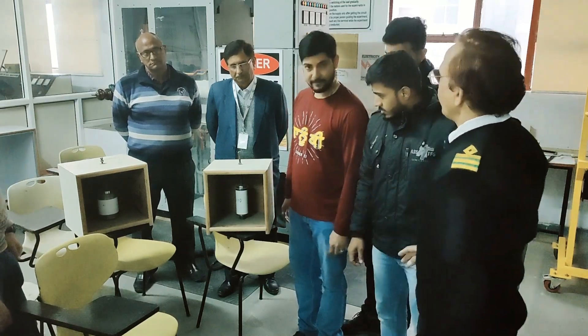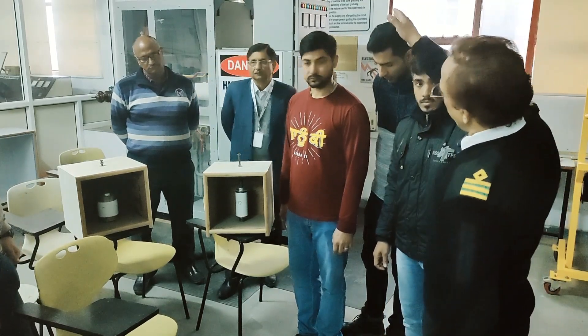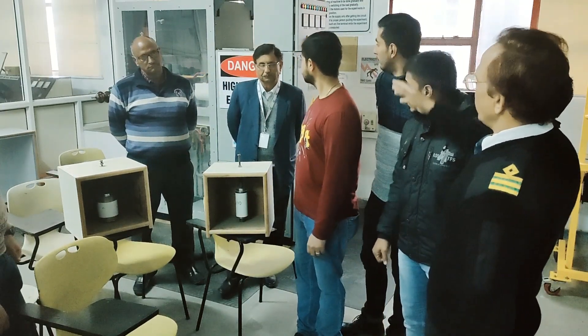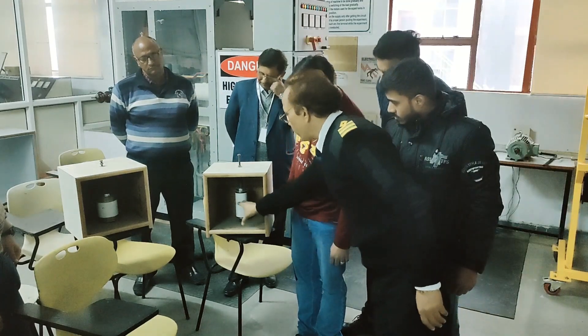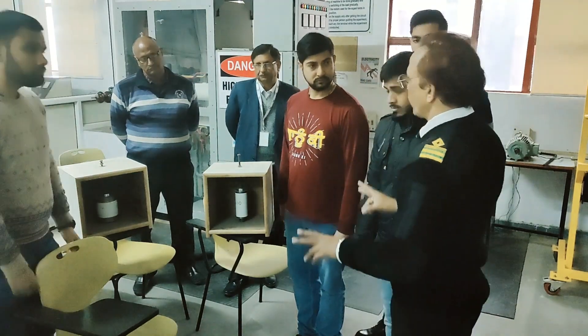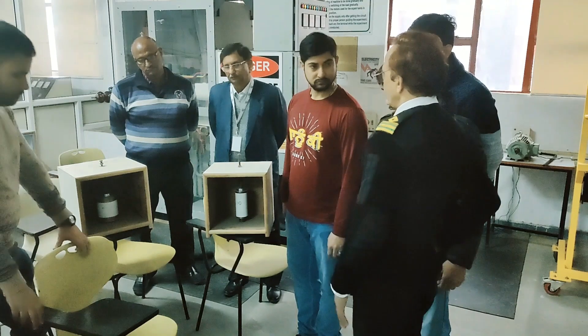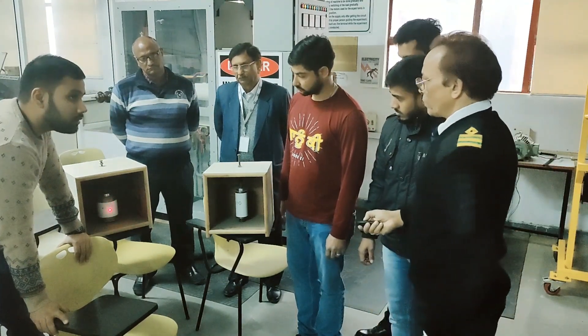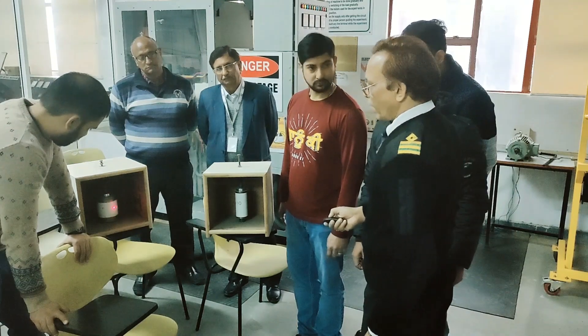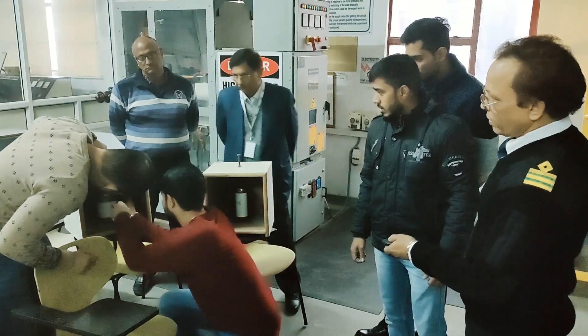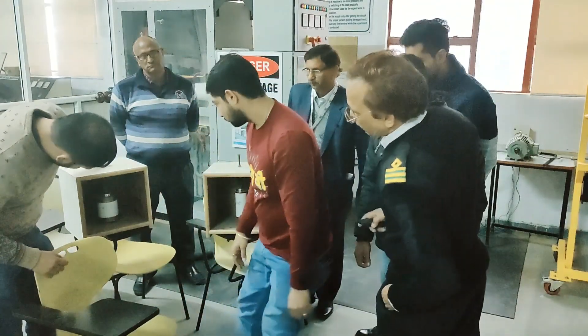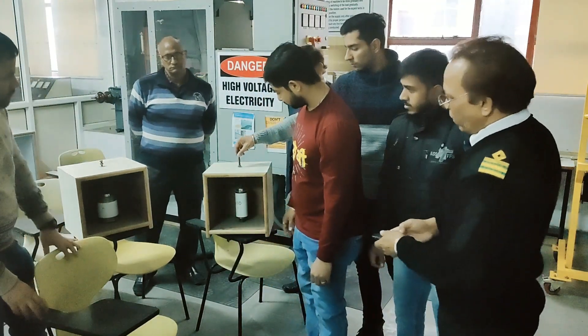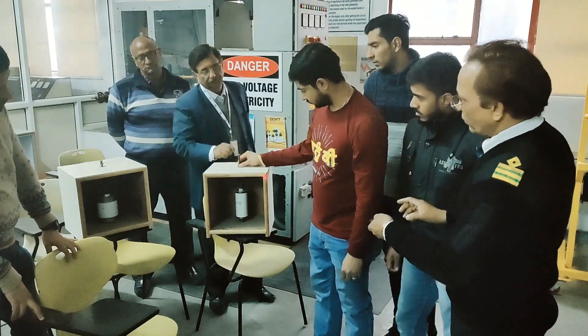In high voltage we are using vacuum circuit breaker. This is our device. In this we are using vacuum circuit breaker. This is the part which is having contact inside. We have two here for demonstration. That another one is defective. There is no vacuum in this and it can be moved. But this is a good one. This contact cannot move up and down.